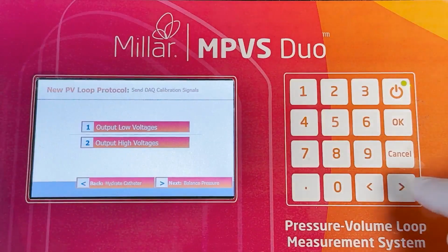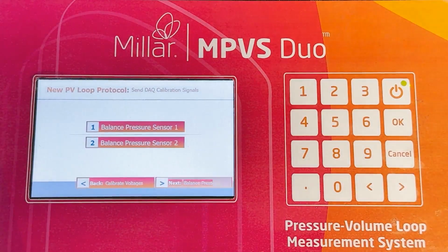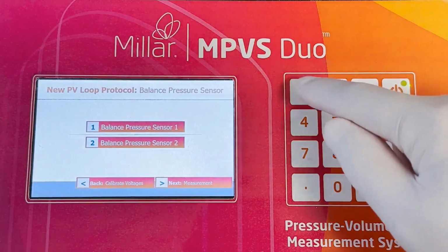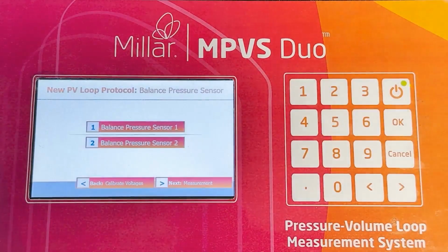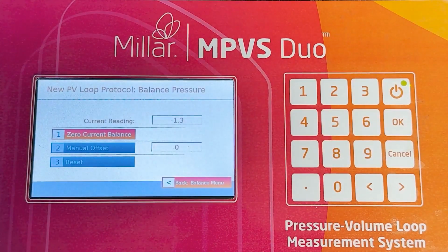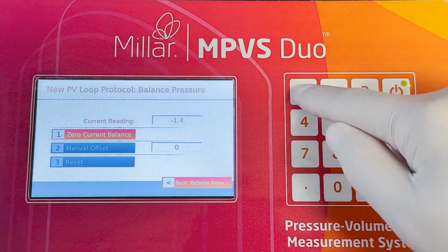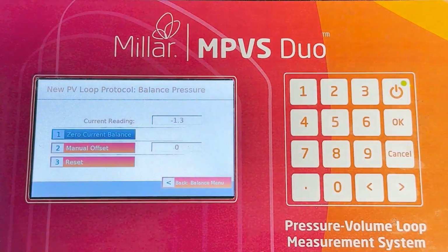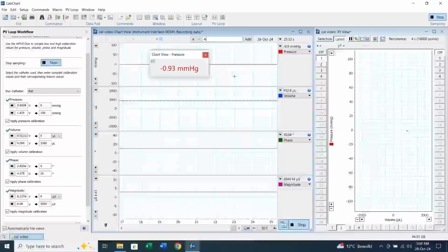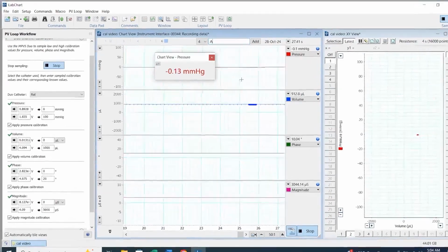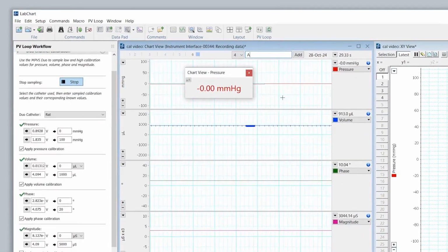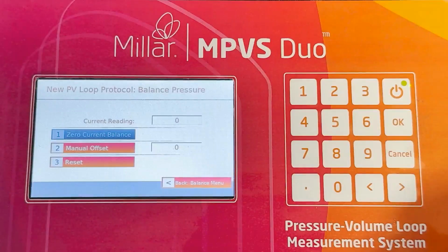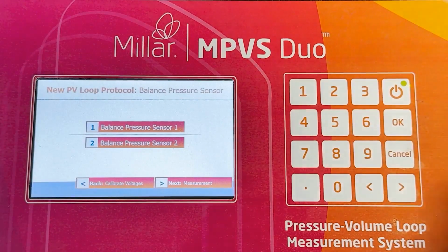On the Duo, press the forward arrow to move to the Balance Pressure screen. Next, press 1 to balance the pressure sensor in the PV catheter. Press 1 to zero the pressure. The current reading on the Duo should drop to 0, as it does in LabChart. Stop LabChart. Now press the back arrow on the Duo to go back to the balanced pressure sensor screen.